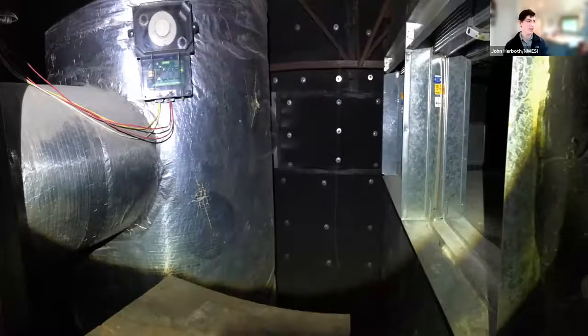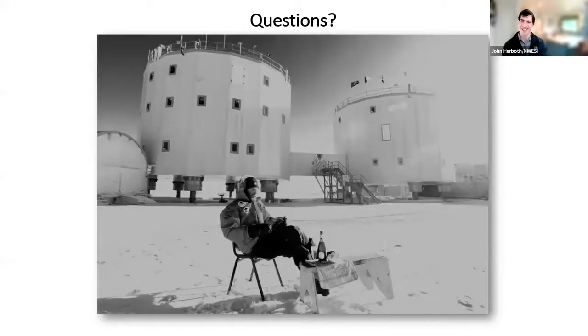And this is my last one. You're going to run into some safety issues for accessing some stuff. This is a shaft, no tie-off points whatsoever. And I'm sure somebody tied off when they went to test that duct detector in that shaft. So we typically ask for as many access hatches as can be used or installed so that we aren't in an unsafe condition. And with that, I wrapped up in record time.